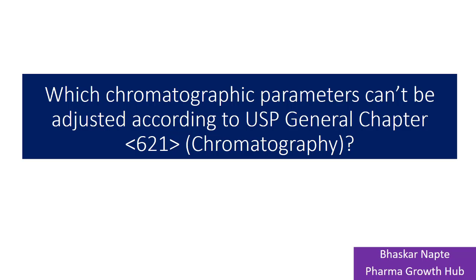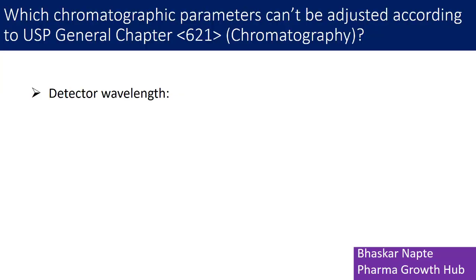My name is Bhaskar Napte. I am the founder of Pharma Growth Hub. Today we are going to talk about those important parameters. The first parameter is detector wavelength, and this parameter cannot be adjusted according to USP General Chapter 621.